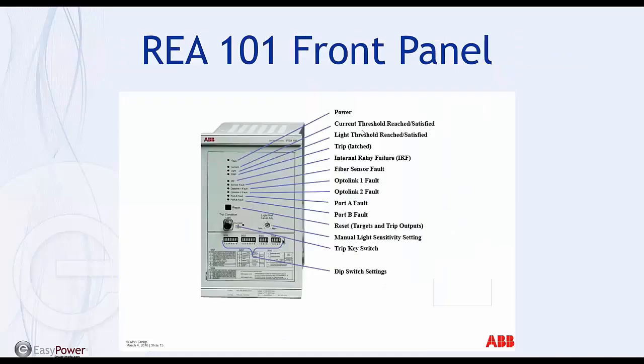Here's the front panel. You have a power light. Here's your status, the current light and trip. You have a relay failure, which also can be controlled by a binary input. You can supervise the loop sensor. You can supervise everything that's connected to that main unit, namely the opto links and the ports. You can reset the targets. You also have a backlight compensation setting right here to avoid nuisance trips. And you have a trip key switch, which is light or light and current. If you're using breaker failure, you need light and current. So I'm probably getting ahead of myself there. We'll see that in another slide when we set up breaker failure.